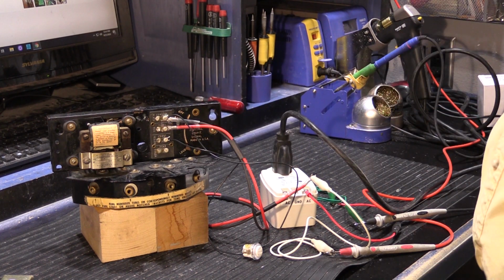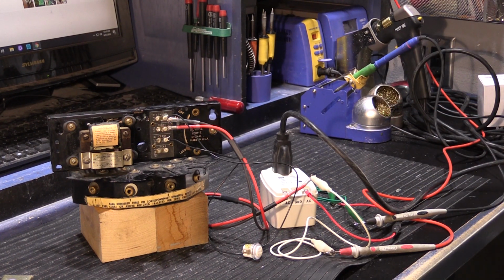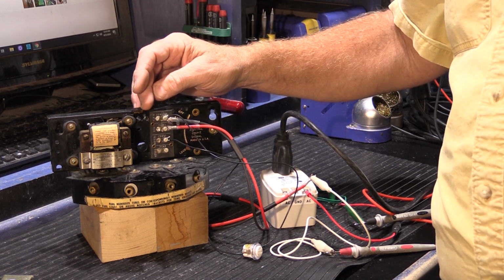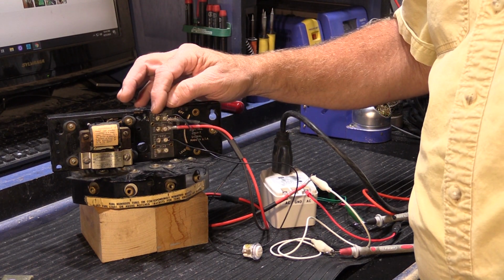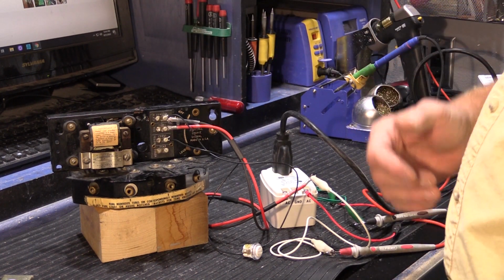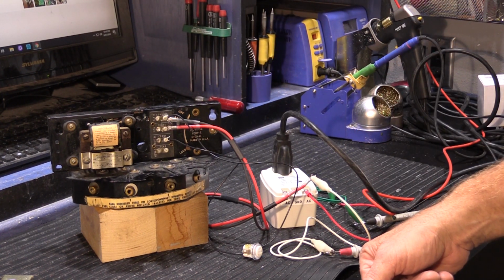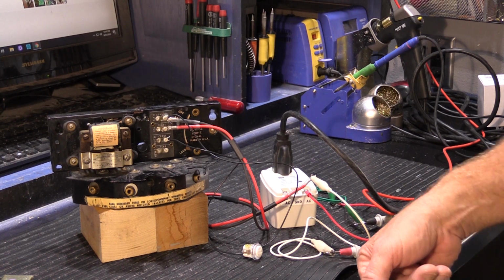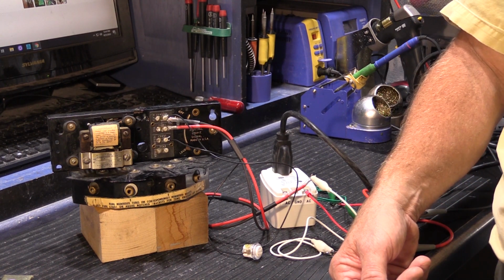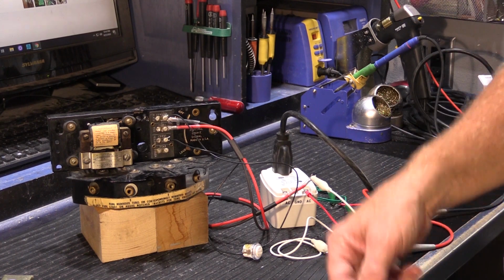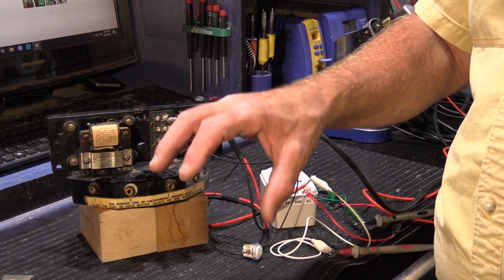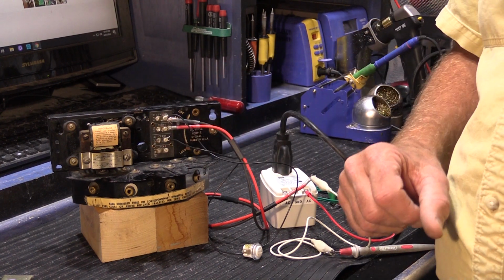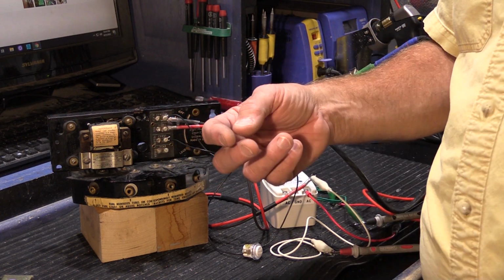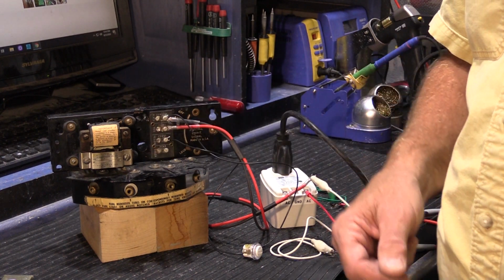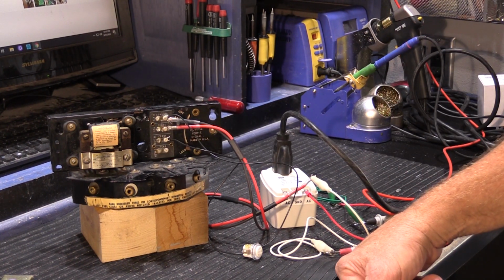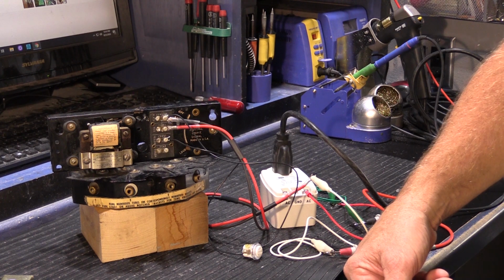Transformers for K model chimes are unusual because back in the day these were powered by NuTone 20 volt transformers, and 20 volt transformers don't really exist much anymore nowadays. Those types of transformers are called class 2 transformers for dry locations, meaning they can be mounted onto an electrical box in your garage or utility room or someplace like that. The low voltage wires connect onto the front and the 110 wires are inside the electrical junction box, and they can be out in the open where people are around because they're safe.